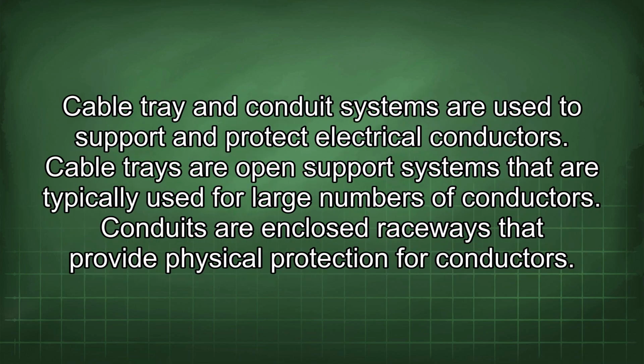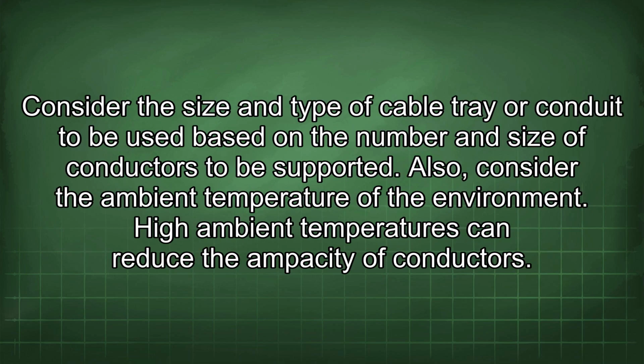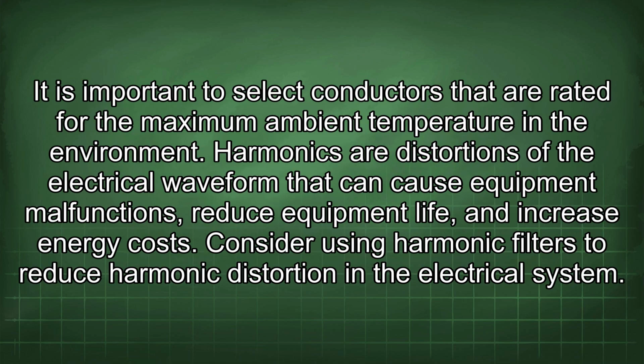these hazards. Cable tray and conduit systems are used to support and protect electrical conductors. Cable trays are open support systems that are typically used for large numbers of conductors. Conduits are enclosed raceways that provide physical protection for conductors. Consider the size and type of cable tray or conduit to be used based on the number and size of conductors to be supported. Also, consider the ambient temperature of the environment. High ambient temperatures can reduce the ampacity of conductors. It is important to select conductors that are rated for the maximum ambient temperature in the environment.